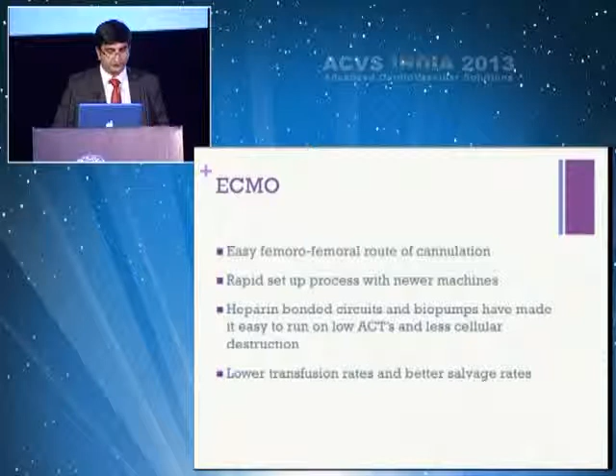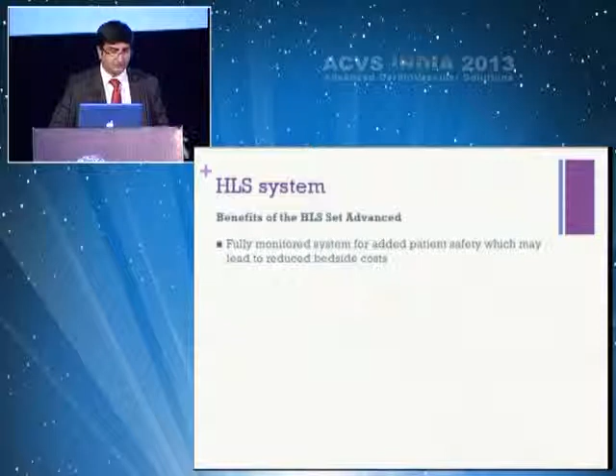So this is an ECMO system that is there. So the benefits of this are, it's a fully monitored system, so patient safety is taken care of. And because of the new technologies, there are no hazards of air embolism, stagnant zones, clotting or cavitation from external sensors, and there are no pressure lines that need to be flushed. You're just running on a flow rate. So if you have a patient who needs a flow rate of, say, 3.5 or 4 liters to maintain a cardiac index of 2.2, you can run on that flow rate.